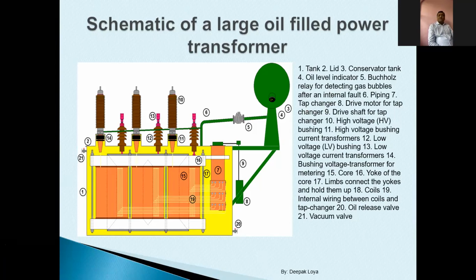Then there are certain protection equipments called the Buchholz relay, which is also called a gas pressure actuated relay. Now when there is a machine, it may malfunction. There may be some faults. There may be some problems with this machine. And due to these problems, the machine may get damaged heavily. The machine is getting damaged, but it may also damage its surroundings.